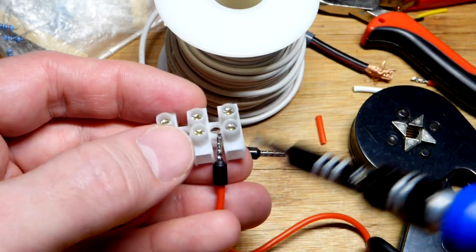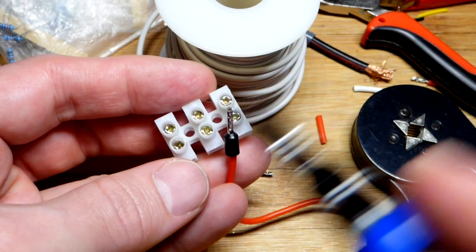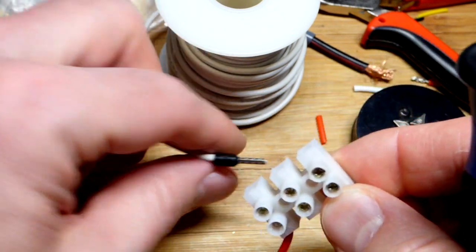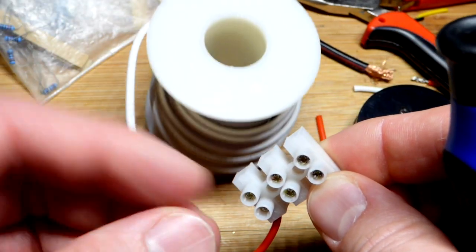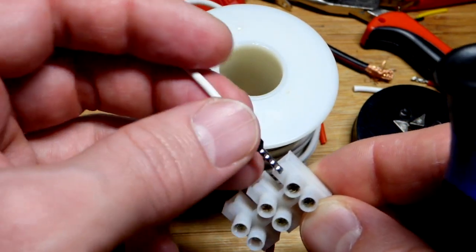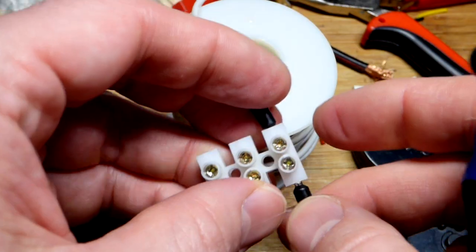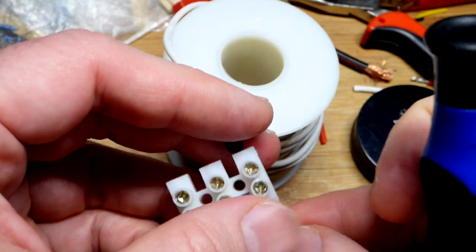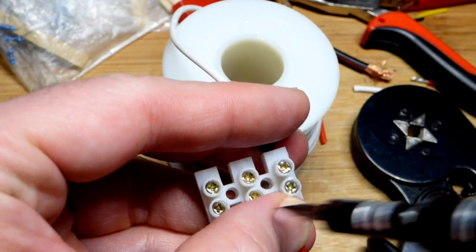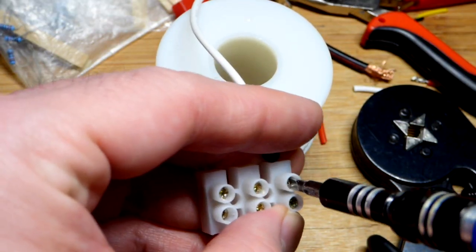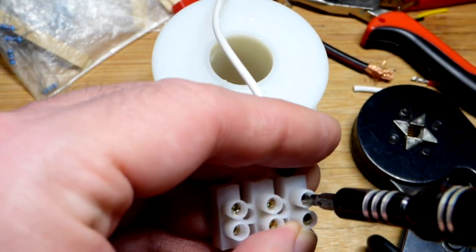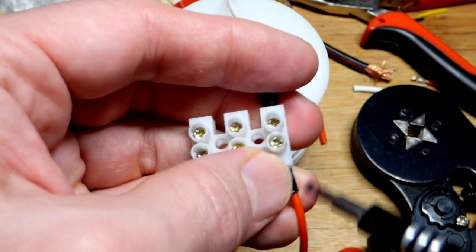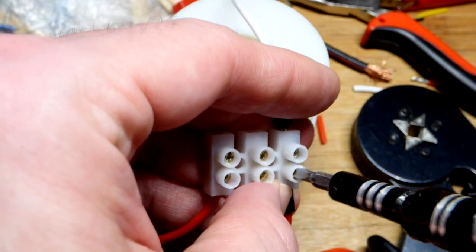So now this is an inline connector that only connects to that one right there. We don't have to worry about these other ones becoming connected. Also I strip the insulation off while the wire is still attached to the spool, that way it holds the strands together. If these were thicker I would screw down one side as a stop, but it looks like we don't quite have enough room. We could trim the ferrules with a snip to make them less long. They're kind of butting across each other enough where they're leaving just a little bit of metal exposed at the end.